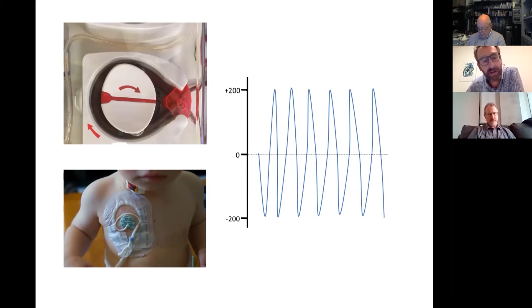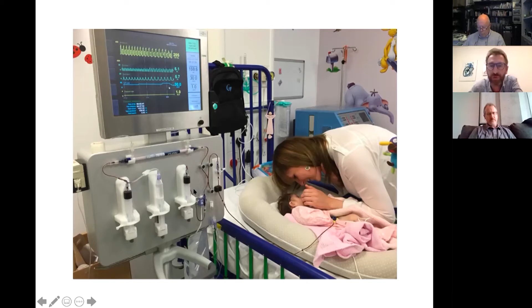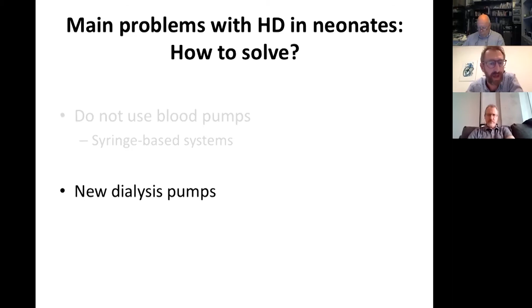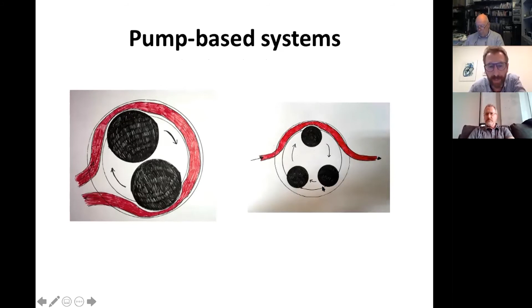So how can we solve this problem? The first thing is to try to not use blood pumps to move the blood when treating neonates or infants. And this is exactly what has been done, for example, by the NIDUS system. The NIDUS system is a system in which the blood is moved using syringes, not using pumps. And the second thing is to try to develop new types of dialysis pumps. So to move from one type of pump that's characterized by having these two big rotors to a new type of pump where we have increased the number of rotors, reduced its size, and reduced the overall dimension of our pump. So from a practical point of view, this is the result.